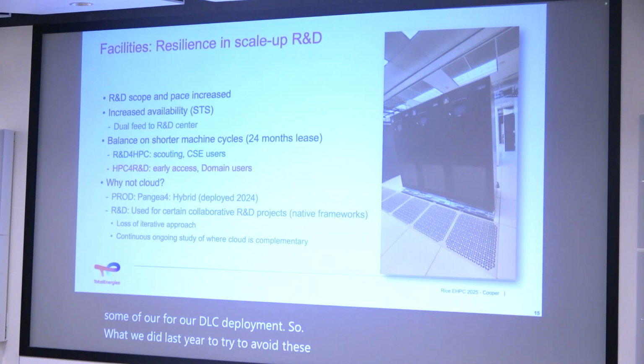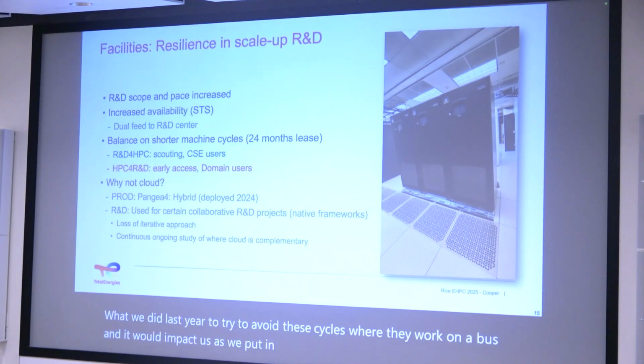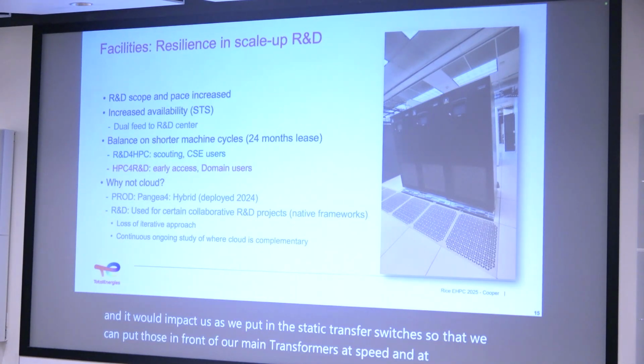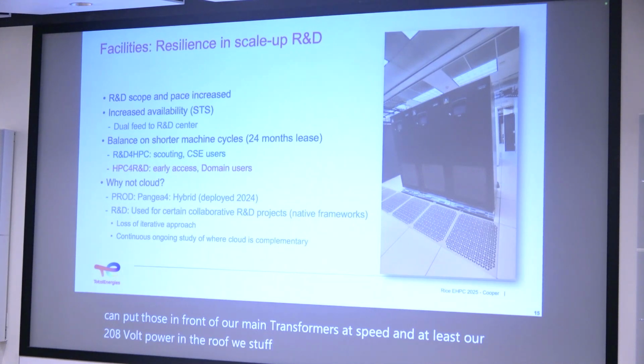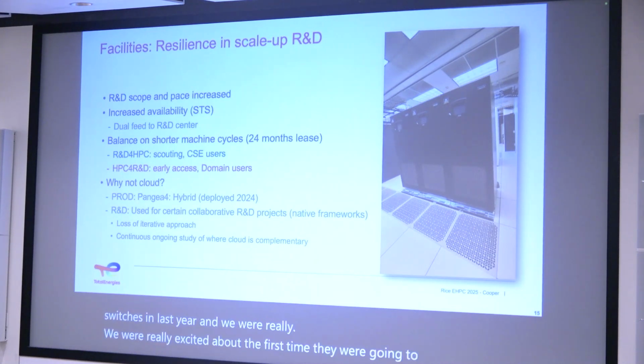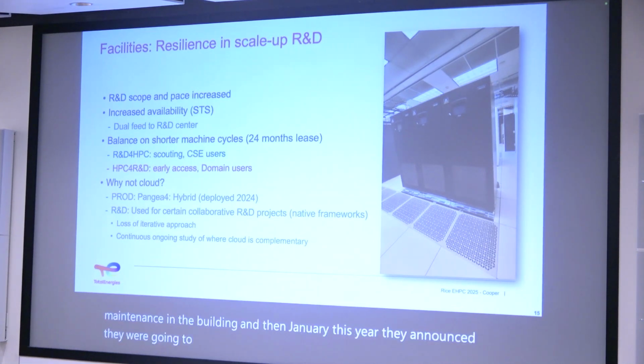So we ended up with a dual MEP room that got power from both sides for our DLC deployment. Last year, to avoid cycles where maintenance on a bus would impact us, we put in static transfer switches in front of our main transformers feeding at least our 208 volt power on the roof. We still have 480 under the floor, which wouldn't be redundant, but we added those transfer switches to the main power feed last year. We were excited for the first time they'd do maintenance in the building—then in January this year they announced they were going to take both buses down.